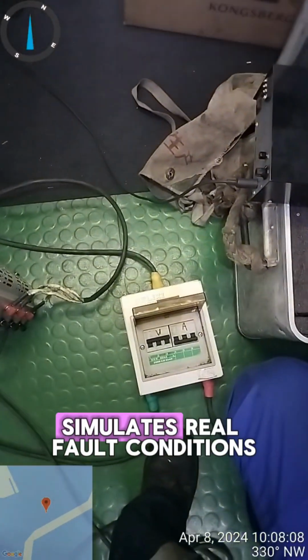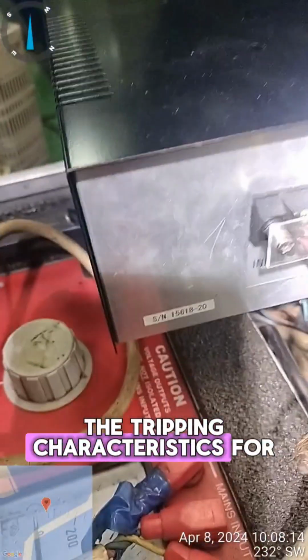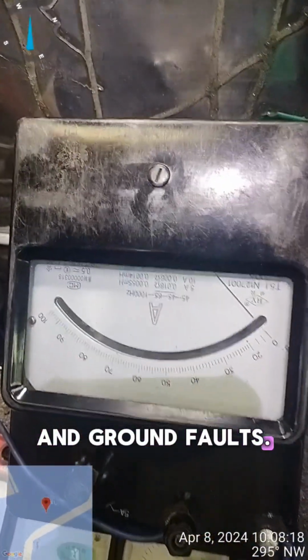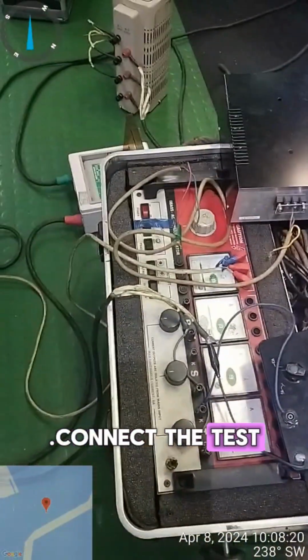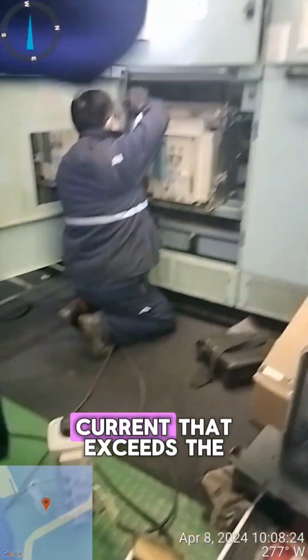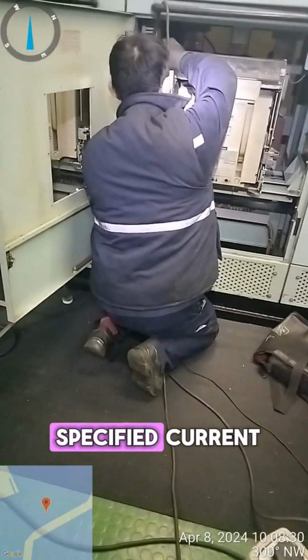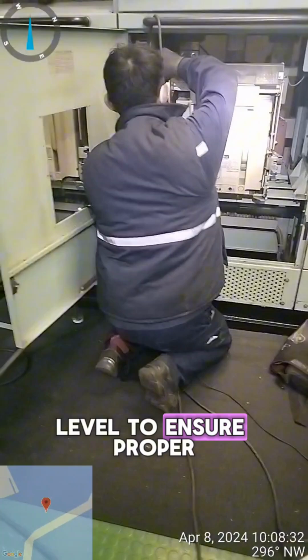1. ACB primary injection test set. Function: simulates real fault conditions by injecting high current into the ACB to test the tripping characteristics for overcurrent, short circuit, and ground faults. Steps: 1. Connect the test set to the ACB terminals. 2. Inject a current that exceeds the ACB's rated current. 3. Observe the breaker tripping at the specified current level to ensure proper functioning.